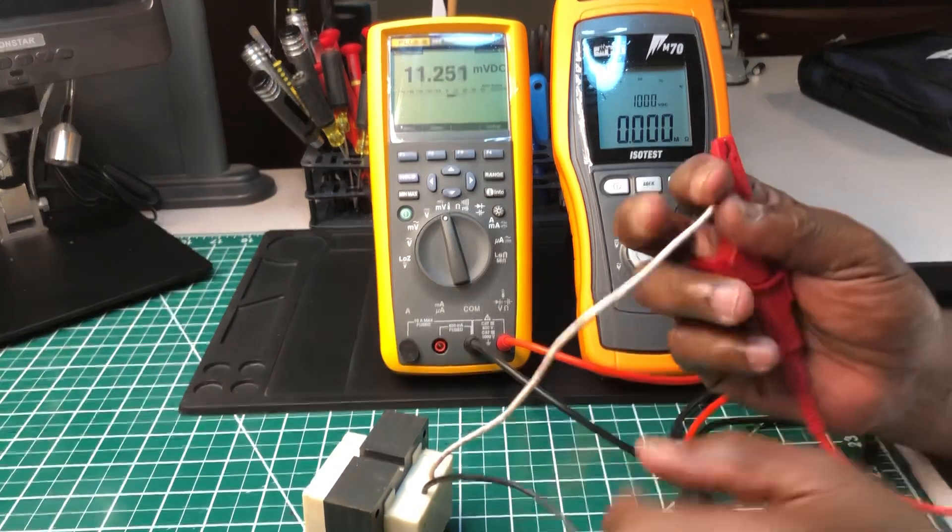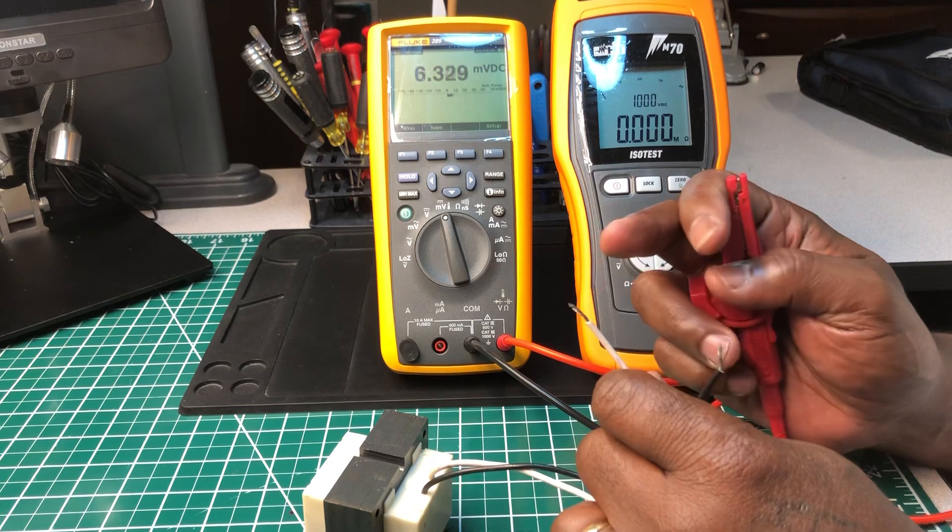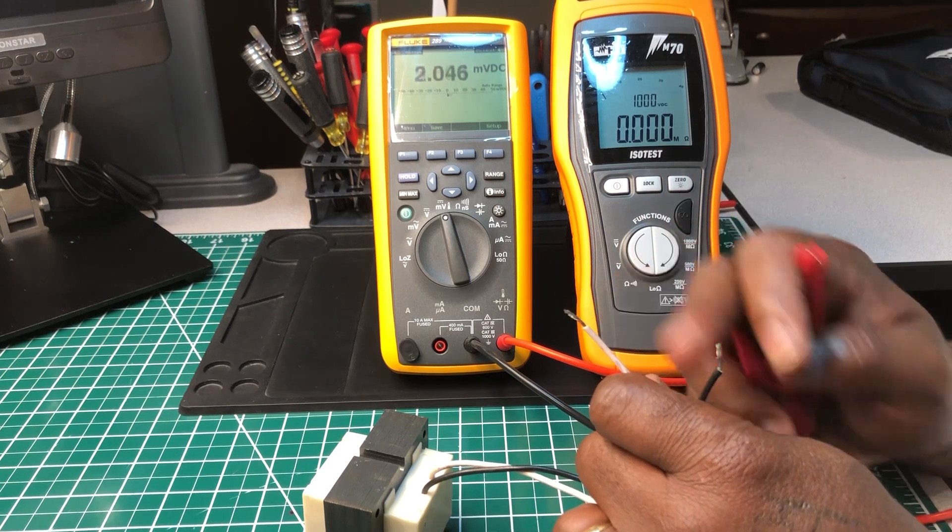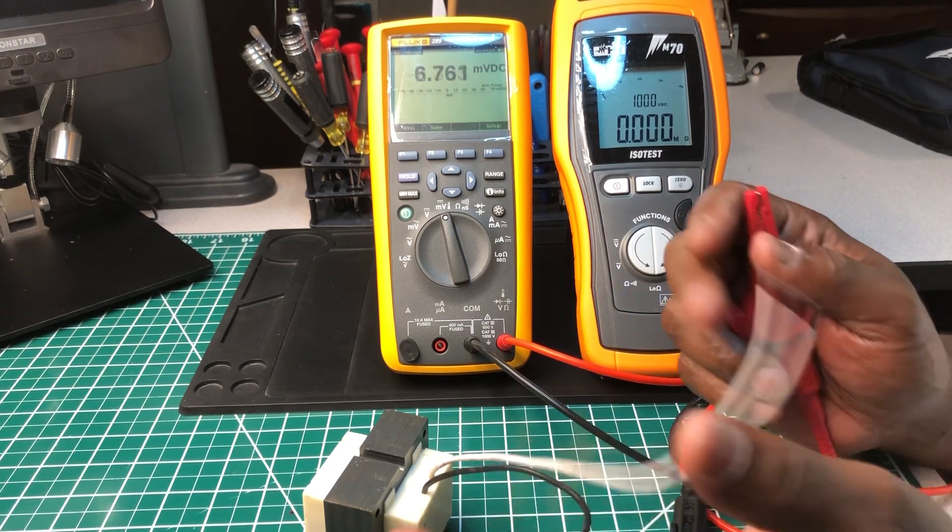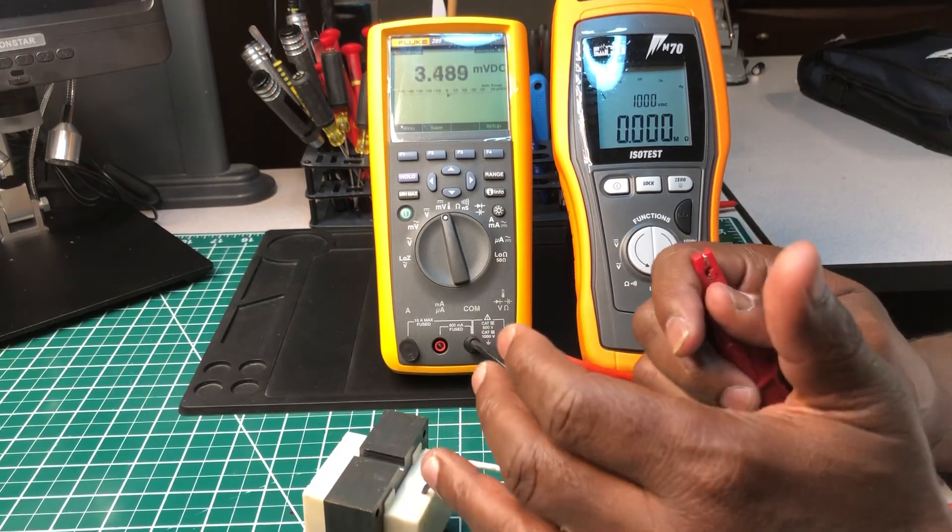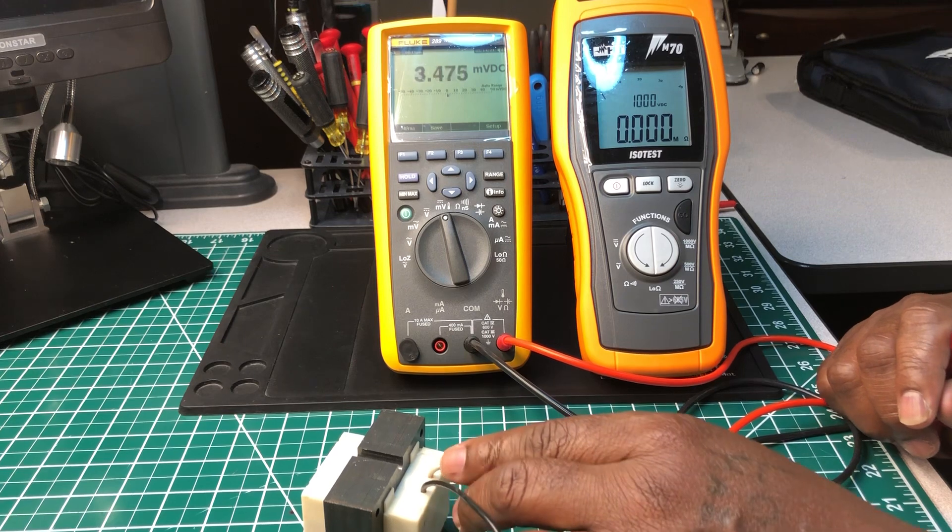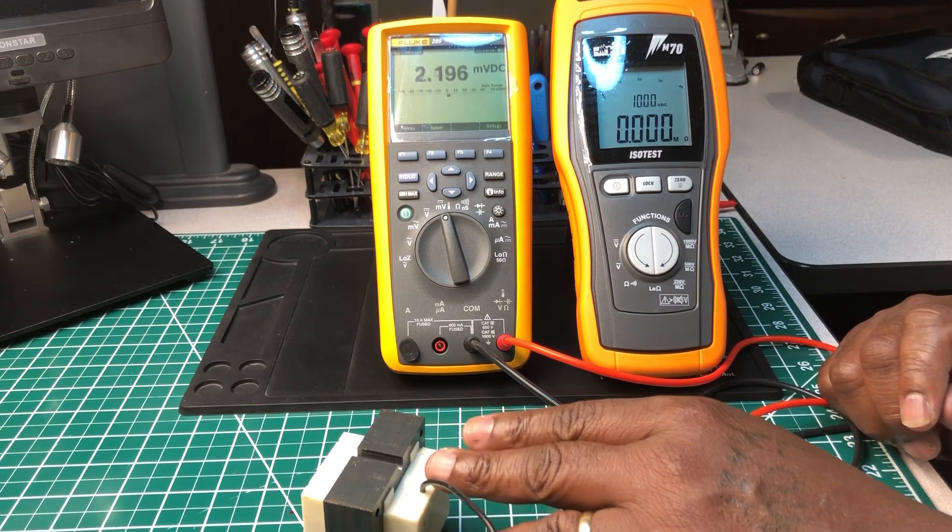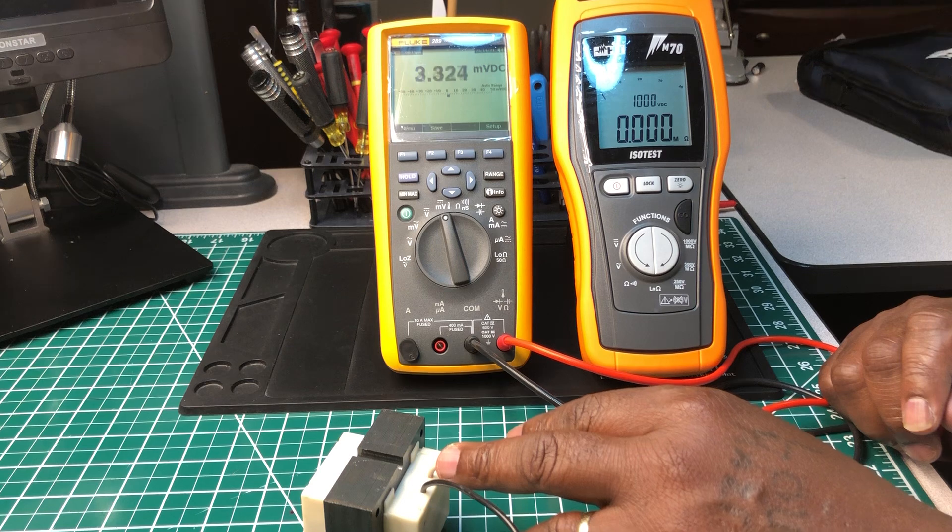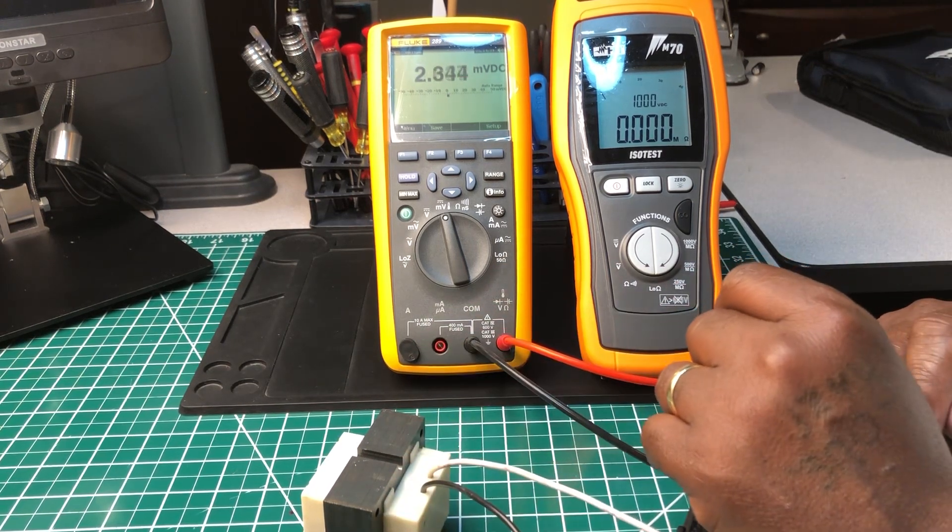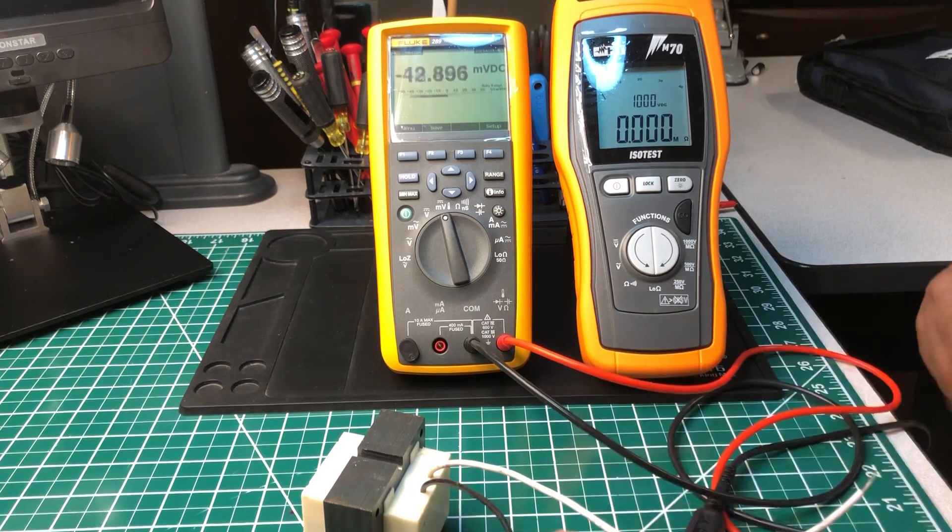If you check resistance and you have no resistance between the two, you know it's good. You do the secondary side the same thing. It's rare for a low voltage transformer to go bad, but if it does go bad, you probably have a short somewhere that caused it to go bad.